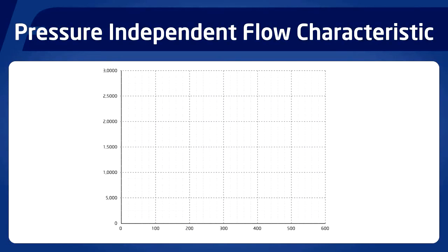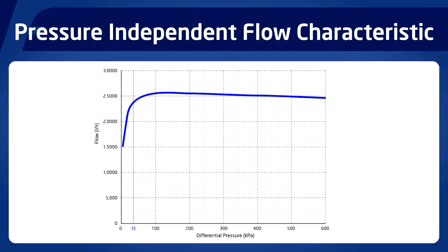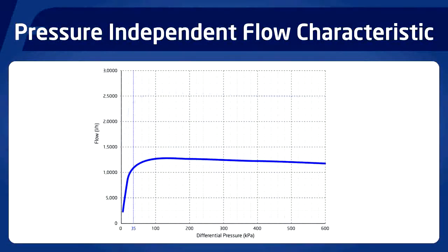This graph shows the relationship between flow and differential pressure. So it can be seen that from the startup pressure, typically 35 kPa, all the way up to the maximum pressure of 600 kPa, once the flow is set at its maximum or somewhere below that, the flow will remain constant irrespective of pressure fluctuations in the pipework, and indeed can only be varied then by the changing actuator position.